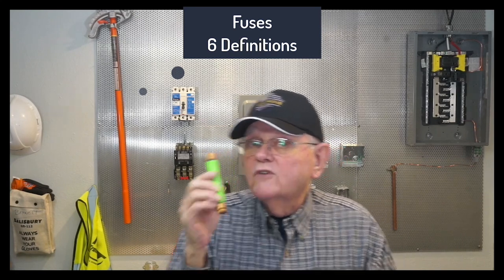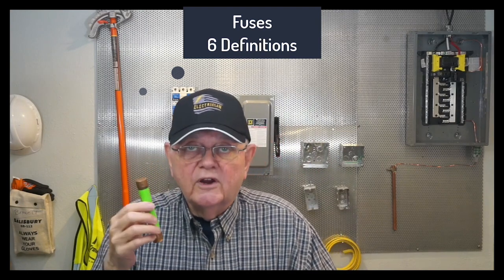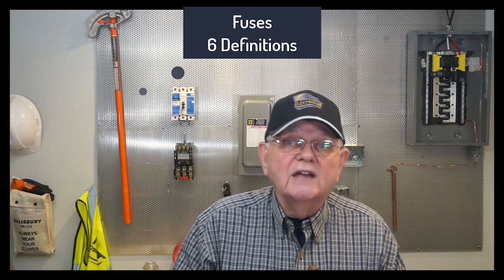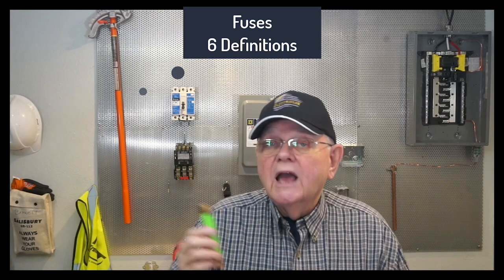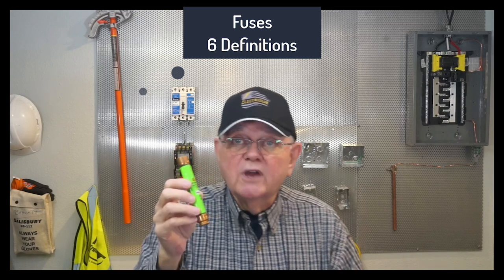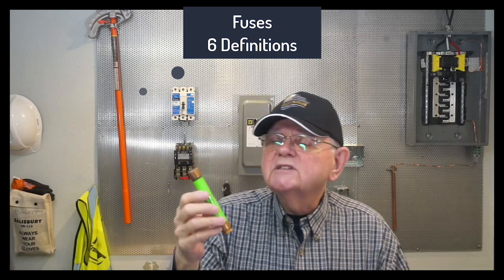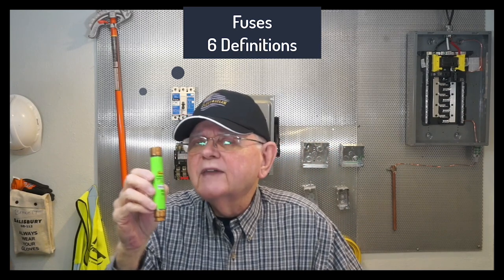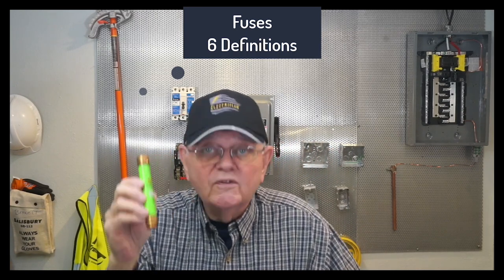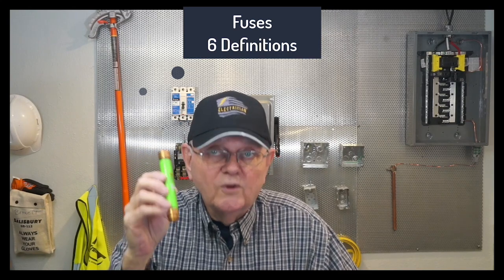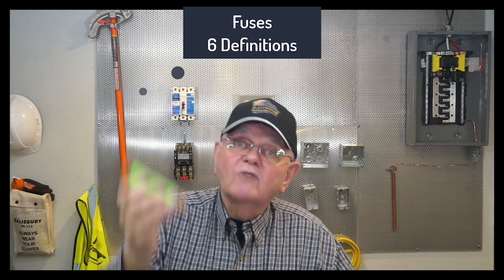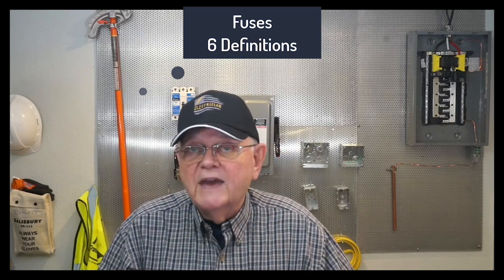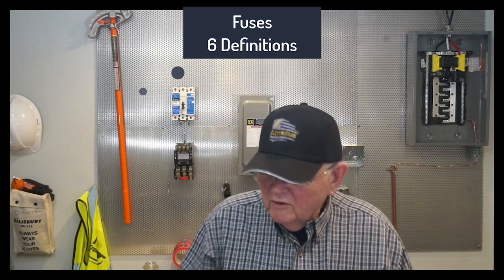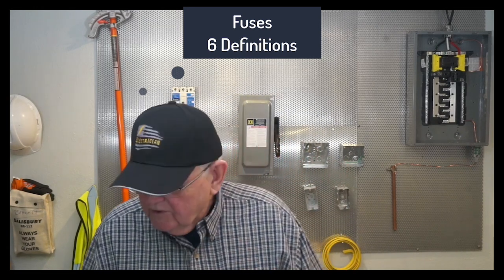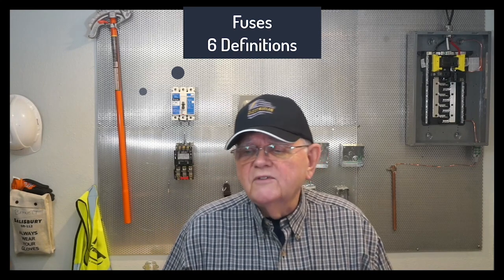If I have a short circuit or ground fault, a large amount of current flow, the fuse opens very quickly. However, when I first energize that motor or transformer, I get a large inrush current. The fuse doesn't blow. On this particular fuse, we'd need to look at the time current curve on it, but it's rated for 30 amps. So it might allow 150 amps for 10 seconds before the fuse would blow. And by then, certainly the motor running current and transformer inrush current should all go back to normal. And then the fuse stays in the circuit for my short circuit and ground fault protection. So different types of fuses. If you get some confusion on that, take a look at your definitions. Pretty well self-explanatory.